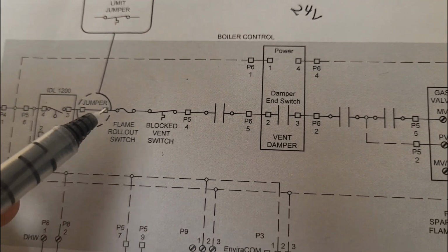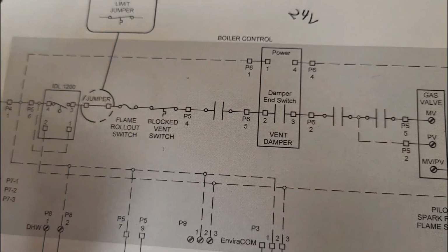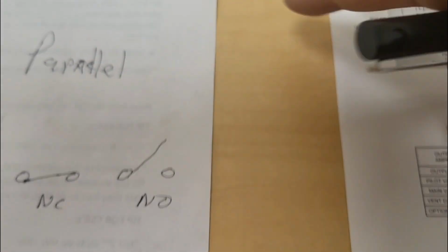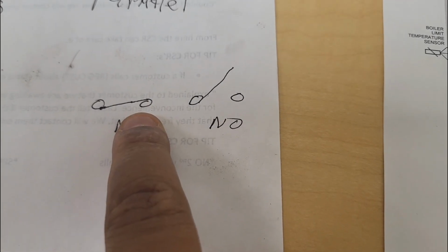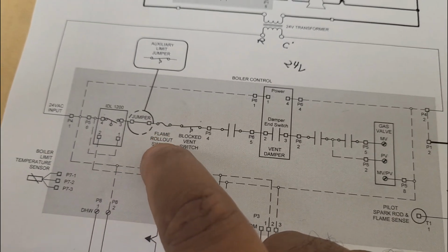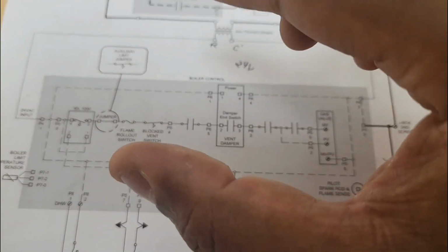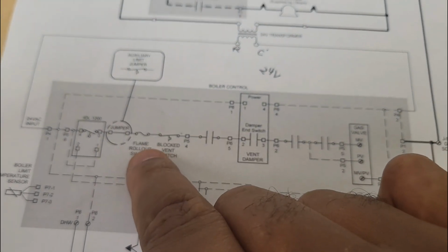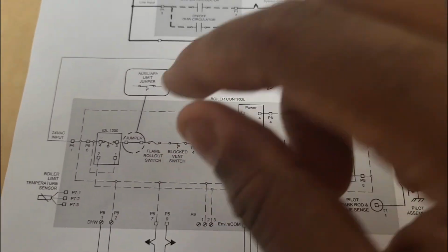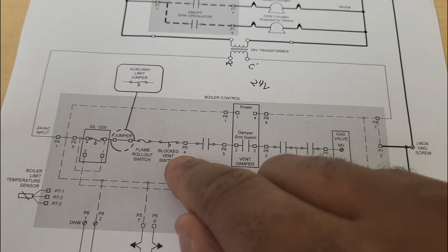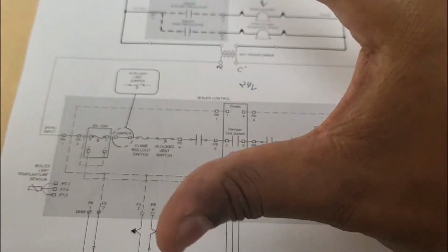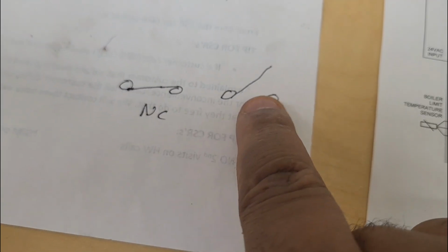But guys, another thing to mention, everything is going to be normally closed until something happens and it opens up. Here's an example. Normally closed, meaning without power flowing through it, it's going to be normally closed, and it opens up on either a rising temperature or whatever causes it to open up. Typically, most of your safeties on a furnace, meaning your rollout switch and your block vent switch, are going to be normally closed, and it's a bimetal that warps whenever it gets hot. Meaning, if your flame rollout switch senses too much heat from the flames backing out of your boiler, or if the block vent switch senses the flue temperature exceeding a certain point, it's going to warp and open up. Meaning, normally closed is going to open up like that.